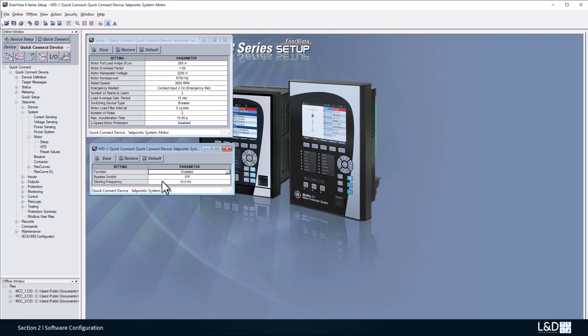In motor applications where the VFD can be bypassed, status of the bypass needs to be set under the bypass switch, and we can choose this bypass switch under the bypass switch setting. When the bypass switch is open, VFD bypassed operand is not asserted. Frequency will be calculated from the phase current A. Frequency element will be inhibited if the phase current is below 10% of the nominal.